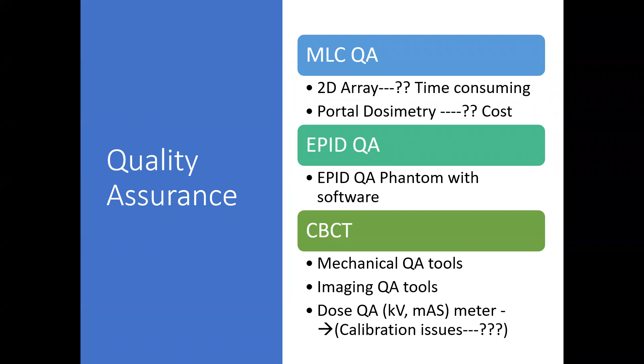So the main theme of this slide is that if we have equipment, for example, if we have MLC, if we have EPID, if we have CBCT, we should definitely have a QA for that as well. We should not be putting these machines into clinical use without QA. If you have an SRS SBRT service, an end-to-end QA system that is CT/MR compatible is a must. Again, if you are to check the patient dosage and you are doing VMAT based SRS SBRT, either you can purchase a 3D array.